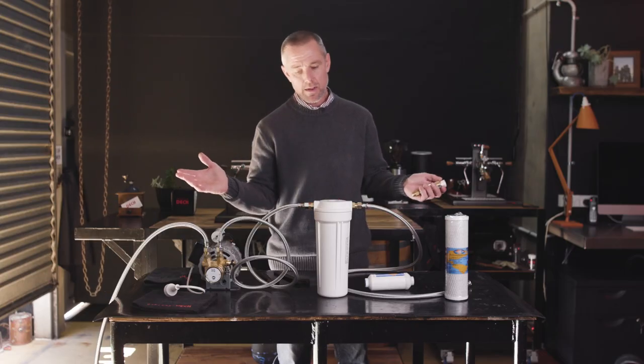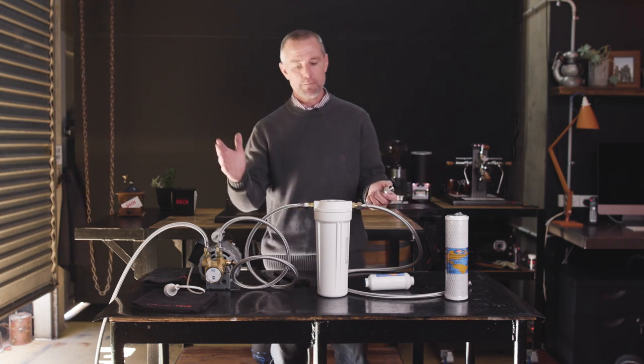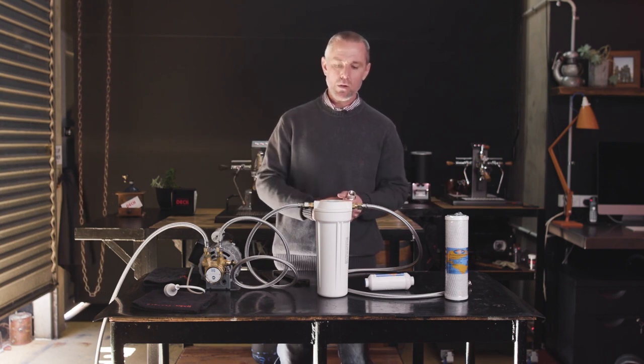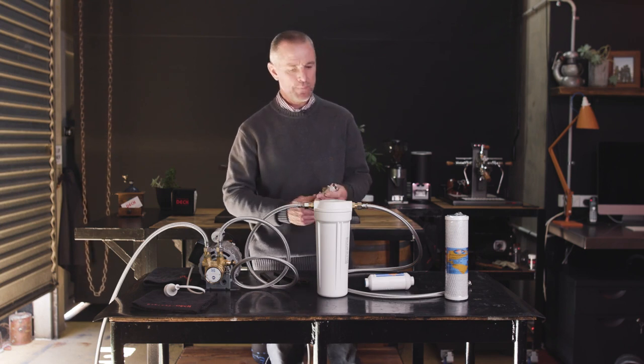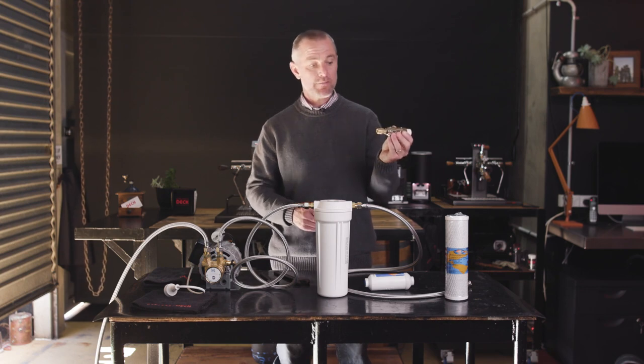What this does is protects mainly your water filter from water surges. These happen in the middle of the night when mains water is being worked on and then turned back on. It can actually blow a water filter apart and can be very messy first thing in the morning for a cafe. So we want to protect that with a pressure limiting valve.